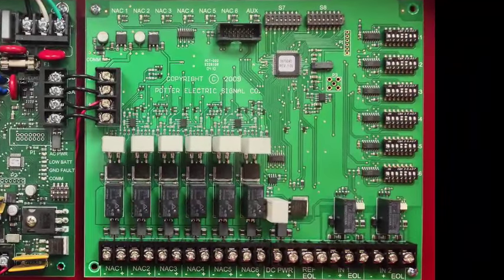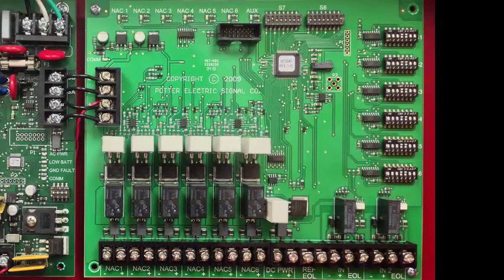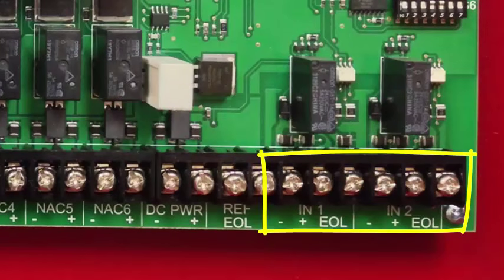Moving to the board on the right, we have several terminals for making your connections, dip switches for programming, and LED indicator lights for troubleshooting. Starting with the terminals on the far right hand side of the board, the two input triggers. Each NAC output can be programmed to follow one or both of the trigger inputs. That programming is done via the dip switches, which we will talk about later in this video.